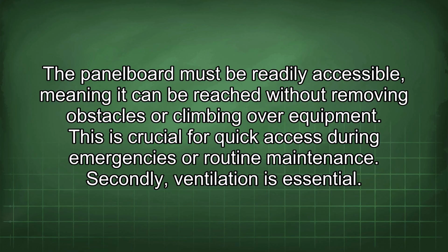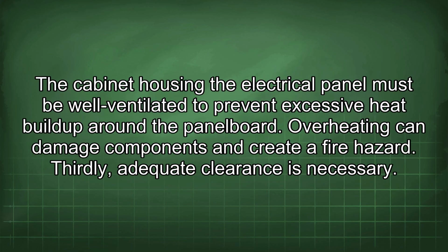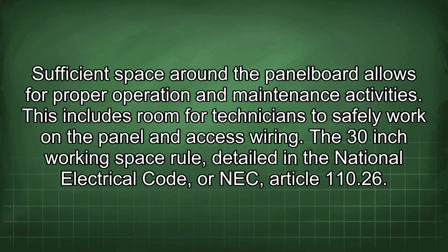Secondly, ventilation is essential. The cabinet housing the electrical panel must be well ventilated to prevent excessive heat build-up around the panel board. Overheating can damage components and create a fire hazard. Thirdly, adequate clearance is necessary. Sufficient space around the panel board allows for proper operation and maintenance activities. This includes room for technicians to safely work on the panel and access wiring.